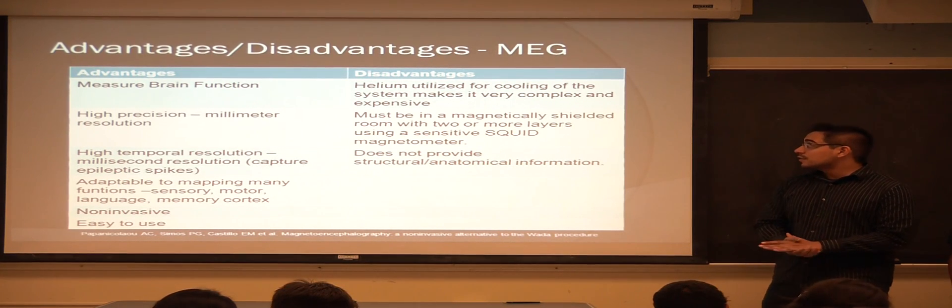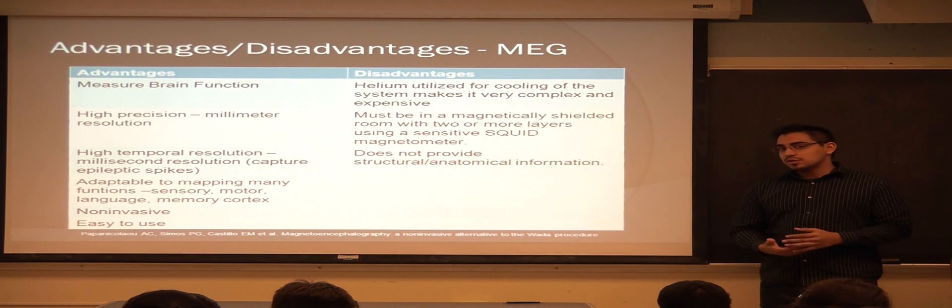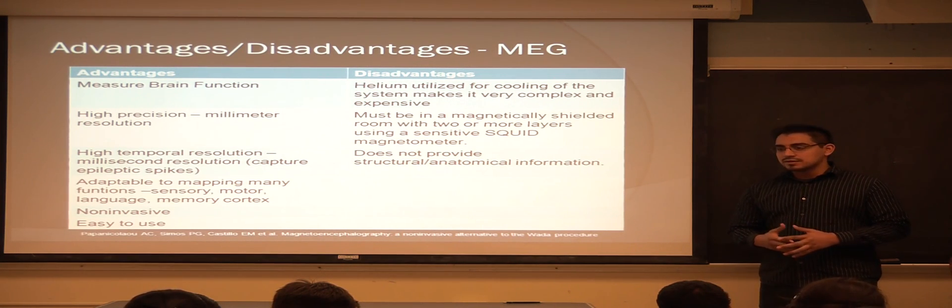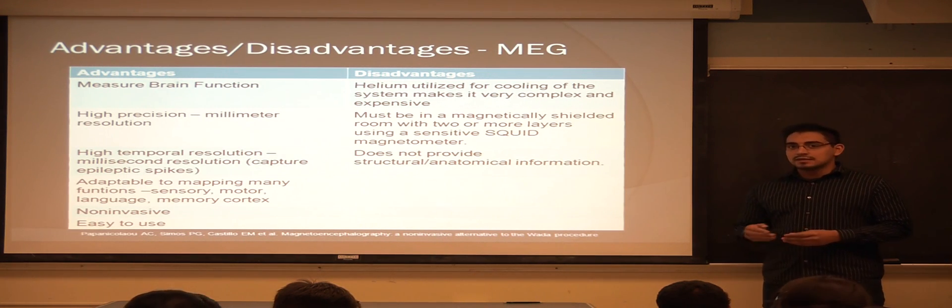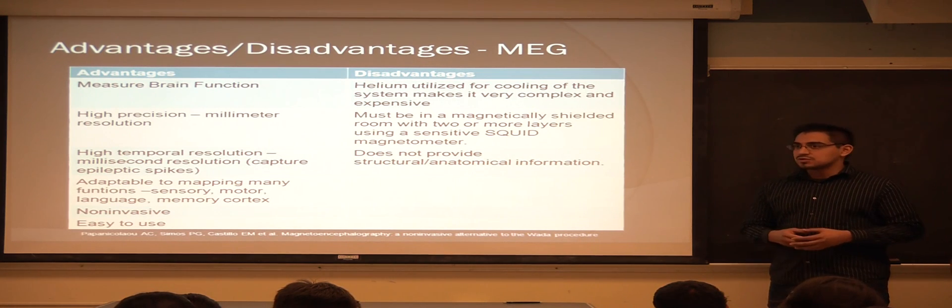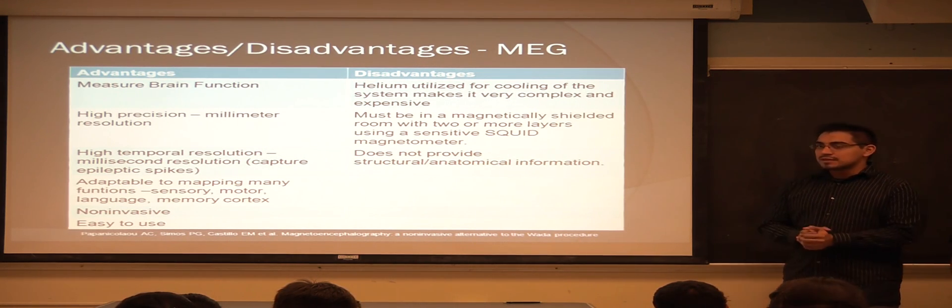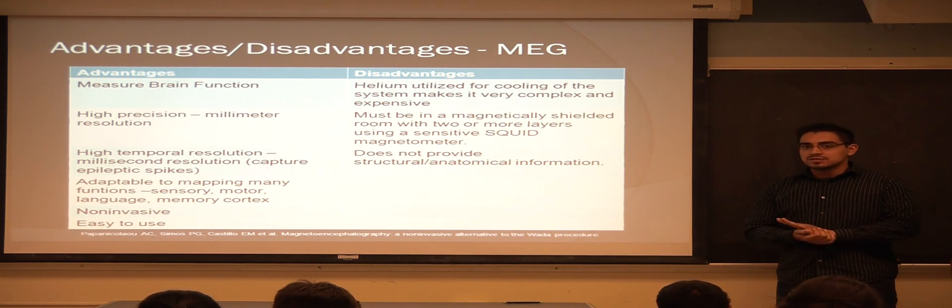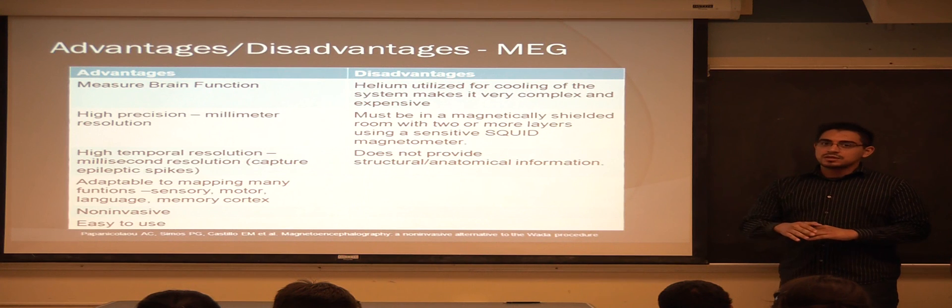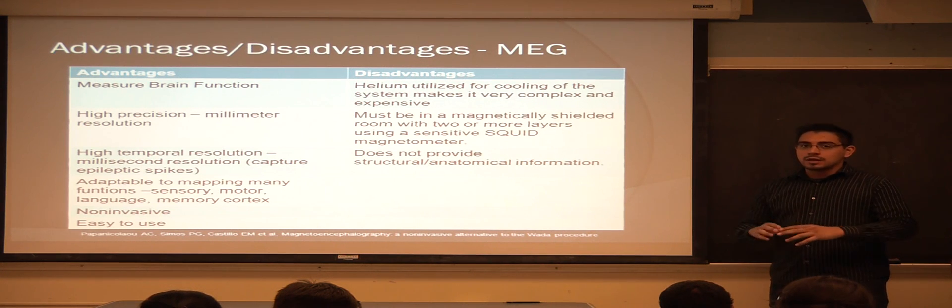But the major disadvantages of the MEG is that, due to the super cooling system that uses helium, it makes it really expensive and also makes the system itself pretty complex. Also, due to the magnetic shielding that you need, due to the small magnetic field that we have in the brain, that shielding also makes it more expensive and less convenient. It also doesn't provide structural or anatomical information that you need. On top of MEG, you need another imaging system to map out the anatomical portion we're looking at.